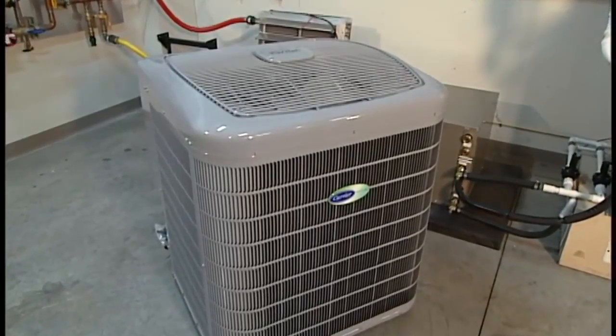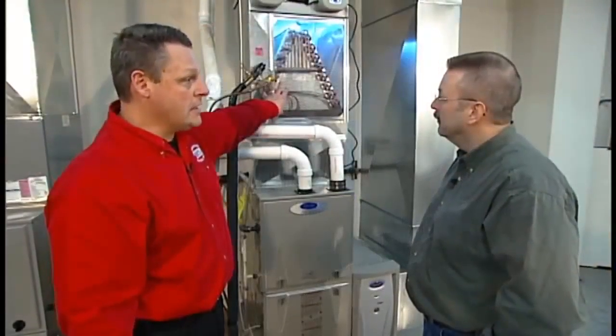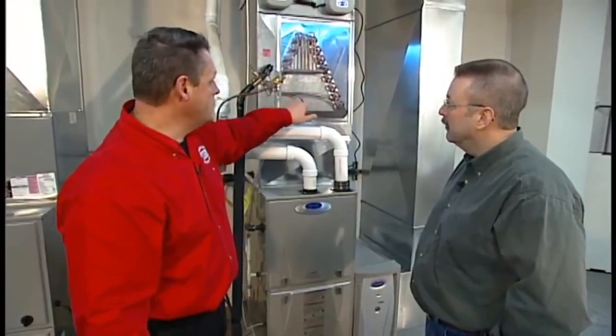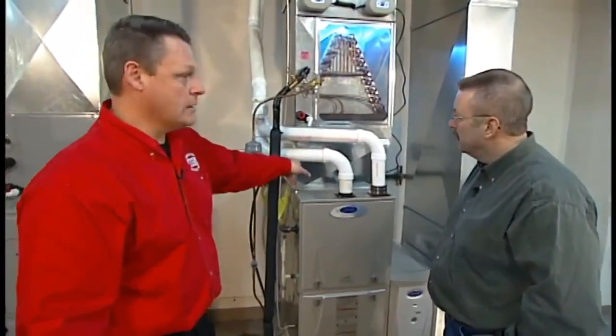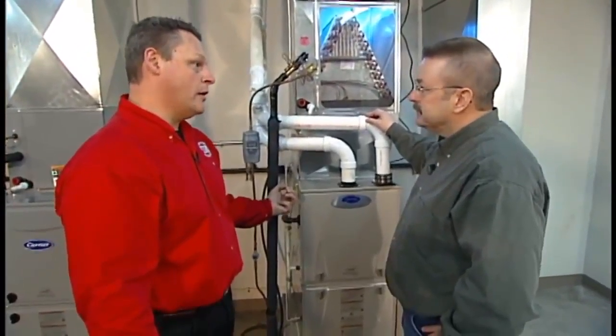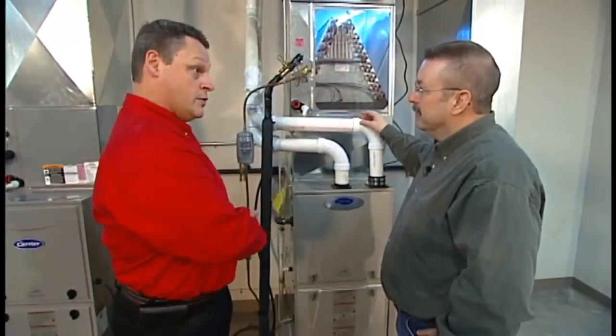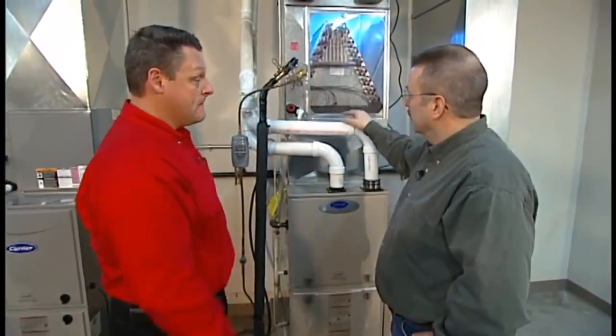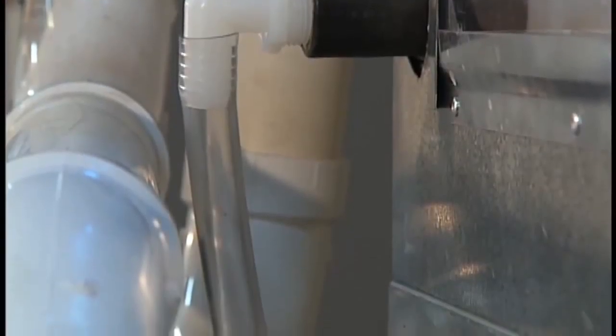We have the A-coil. What this does is it extracts the heat out of the indoor air. Also, it removes humidity, and that's what the condensate line does: it drains the water that we wring out of the air and gets rid of it down through our floor drain. So in the warm summer months, when I see water coming through that clear tube, it's a good thing. That's a good thing.